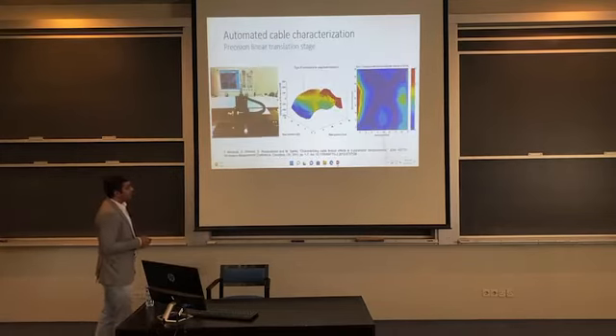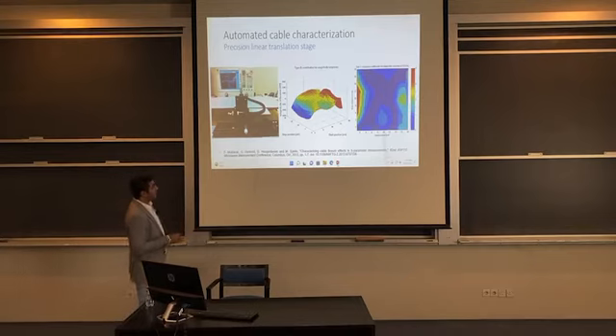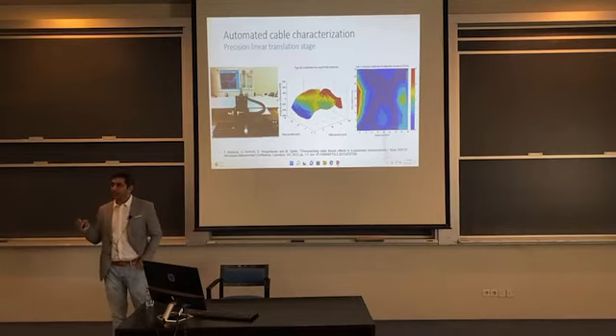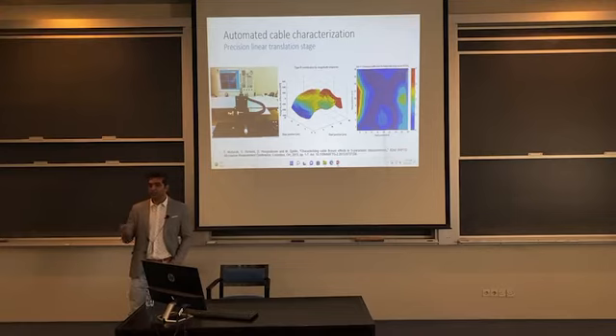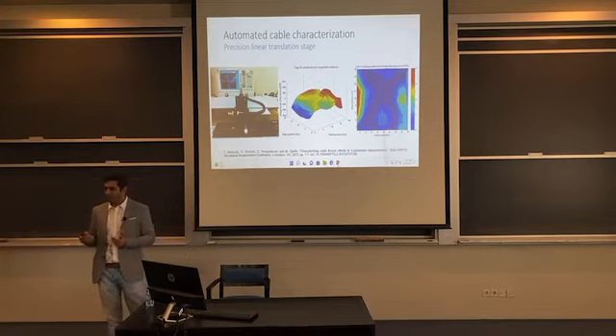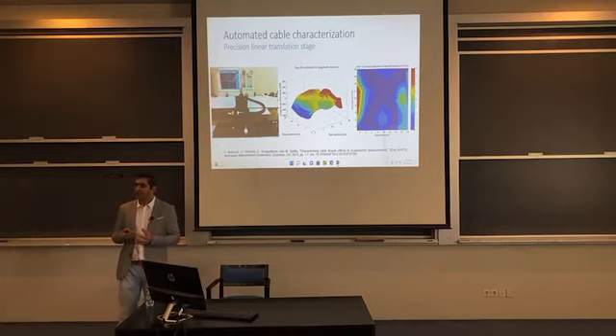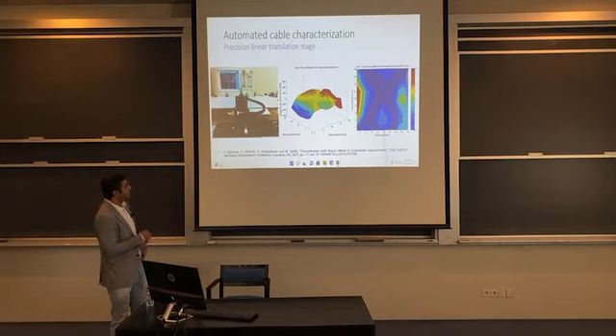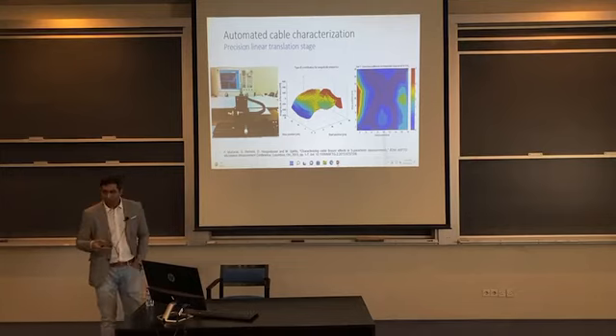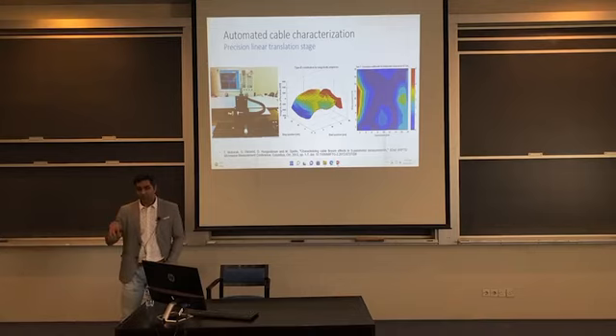So cables, which I was talking about, we can buy one of the best cables in the world, but still they are imperfect. They still introduce errors. And it's all about measurement and accuracy. So every element that's involved in the system, we need to individually characterize its influence. So how do we characterize the influence of the cables? We build this very nice robot here, which is basically a motorized cable stage. We mount the cable and we move the cable in a very specific way, the way that we also use it in the measurements.